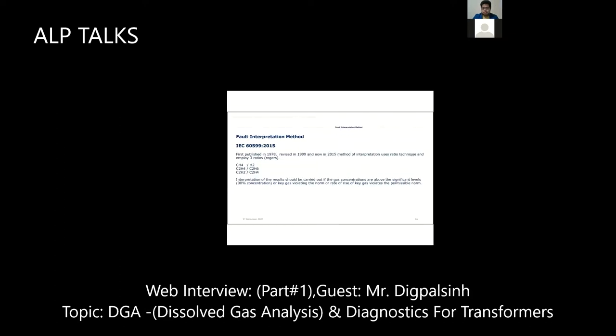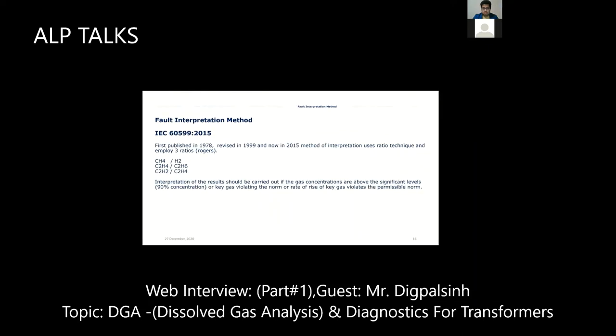After that, we will discuss IEC 60599. IEC has revised it three times. First they published it in 1978, it was revised in 99, and now in 2015. IEC has defined three gas ratios. First is methane and hydrogen, CH4 and H2. Second is C2H4 and C2H6, where C2H4 is ethylene and C2H6 is ethane. And the third ratio is C2H2, which is acetylene, and C2H4, again ethylene.